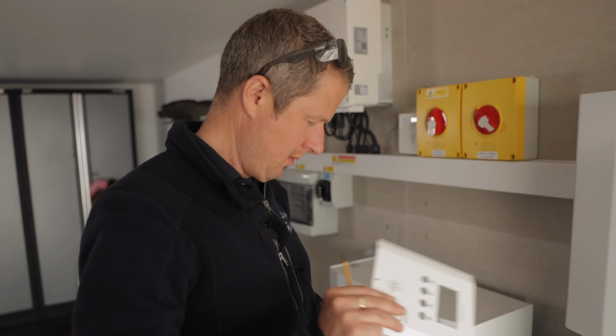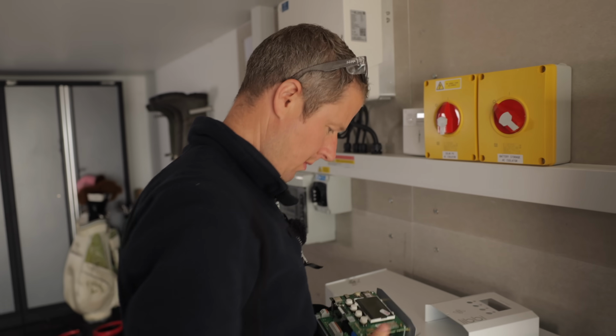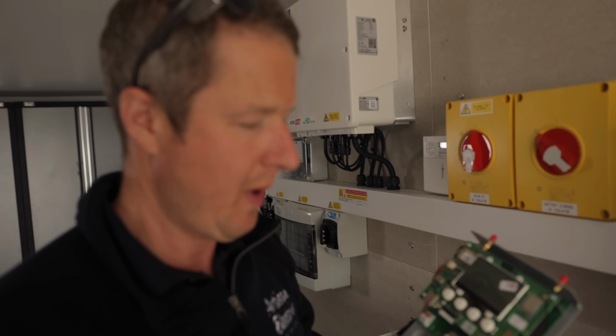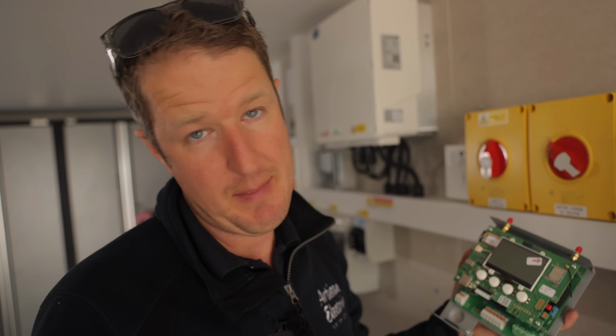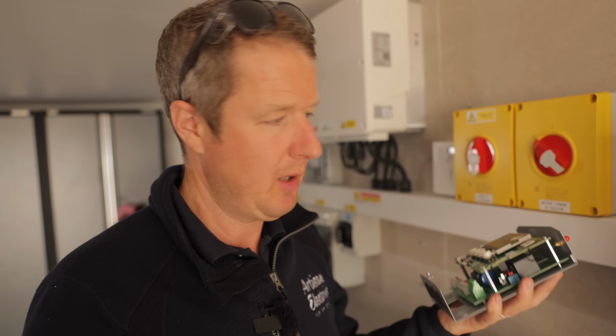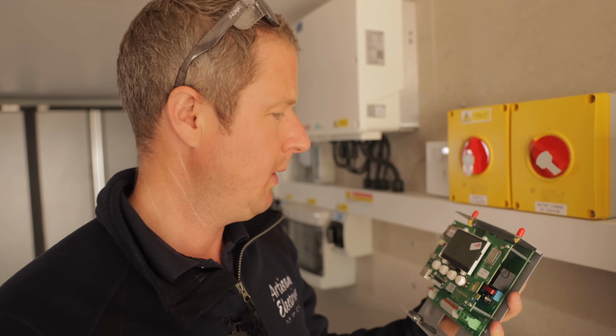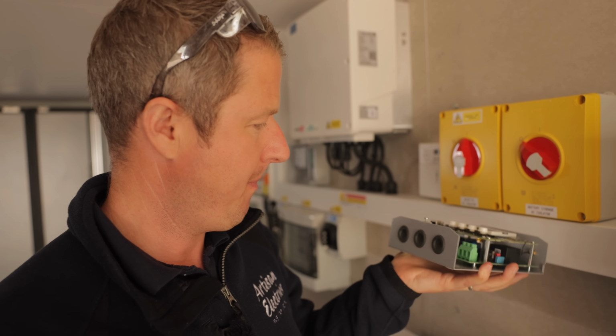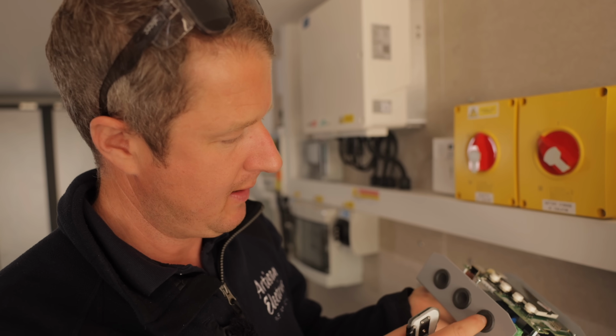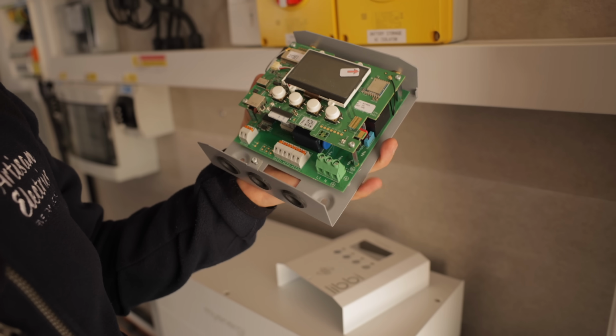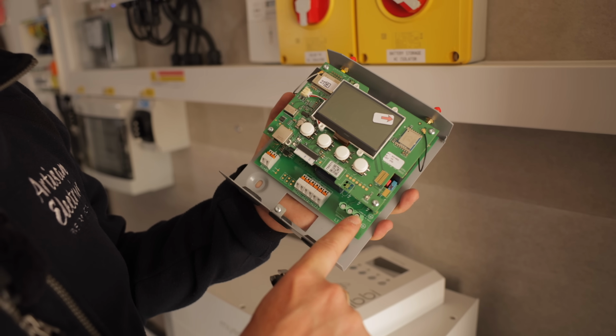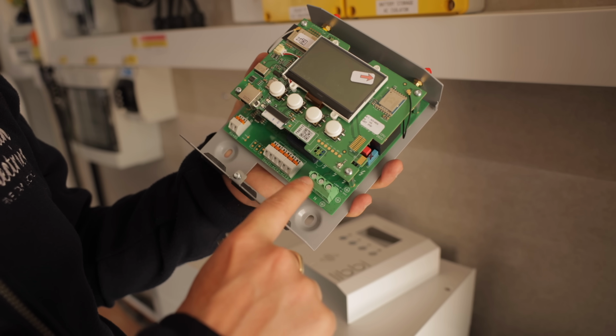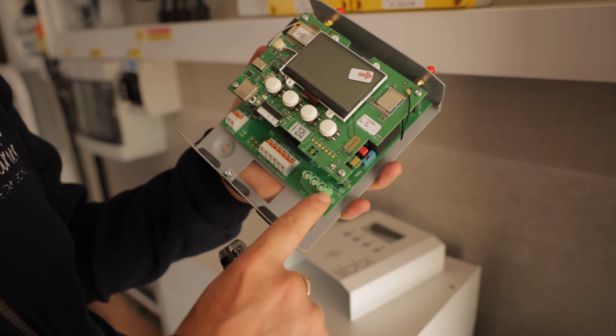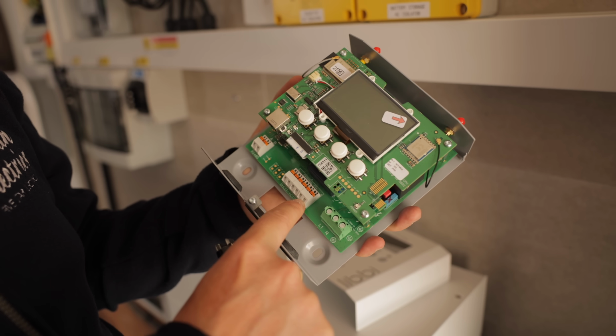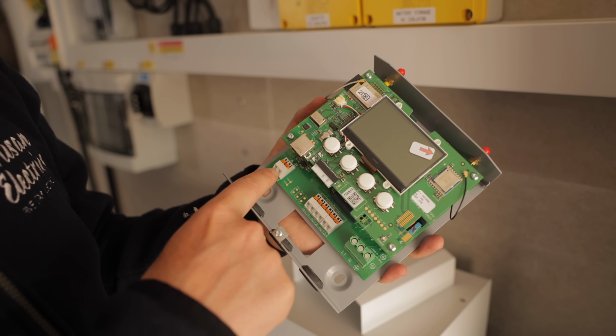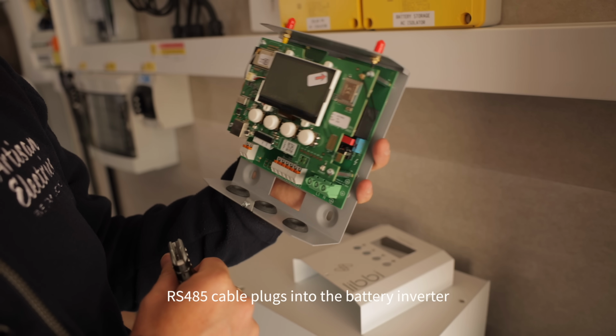So the Libbi controller needs to be mounted indoors. It can't be mounted outdoors because it's not weatherproof. The Libbi equipment can be mounted outdoors if you have to, but I would always recommend inside if possible. Other thing about this, it's got these grommets in the bottom. You've got various cables that need to go into this. You've got power, so you'll need to feed it from a 3-amp fuse connection unit. Then you've got 3 CT connections that can go into it. And you've got the RS485 cable which plugs into the battery.